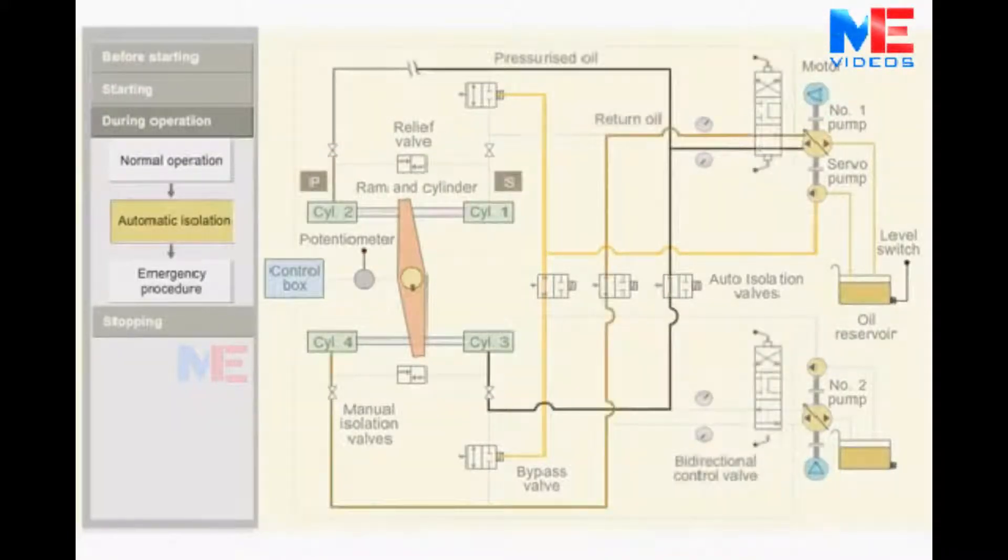Consider during the operation, there is a fracture in one of the pipes. The oil starts leaking and oil level starts dropping in the oil reservoir. The low level alarm is raised. If the leak is severe, then low level alarm sounds and the system gets automatically isolated in the following way.